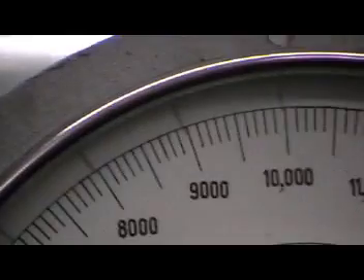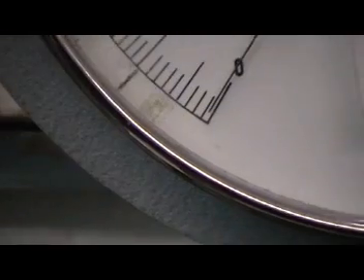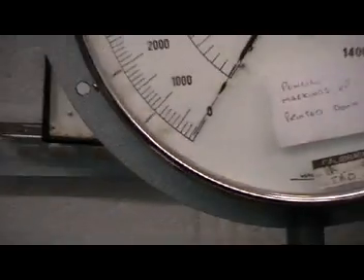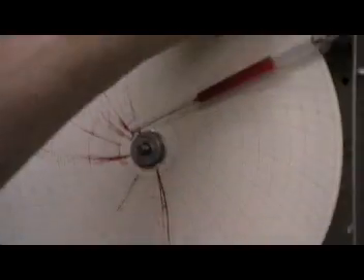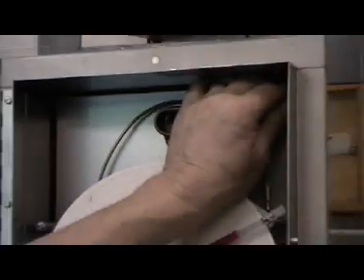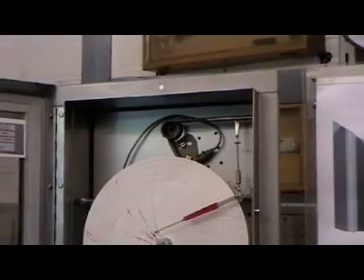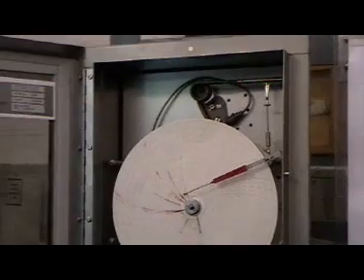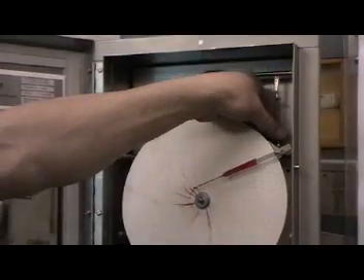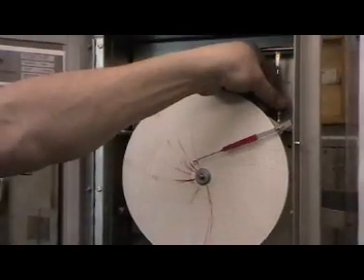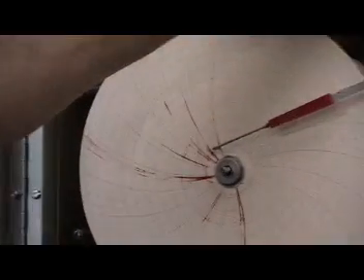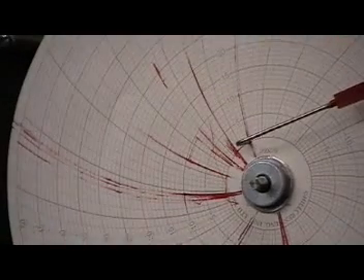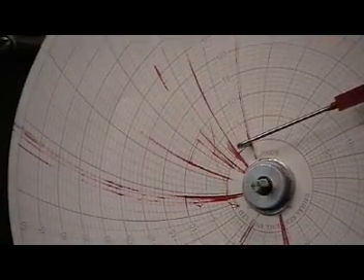And now we need to increase the span slightly. So, again we're adjusting that pivot point out. We check the zero slightly, lock the zero off. And the same again.